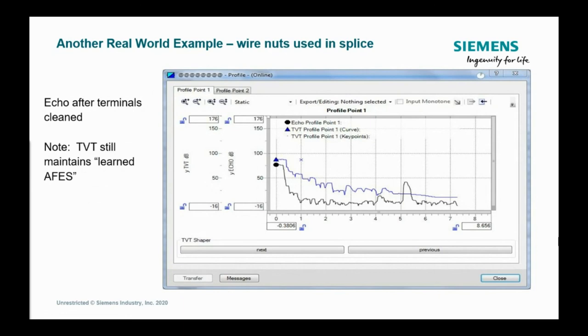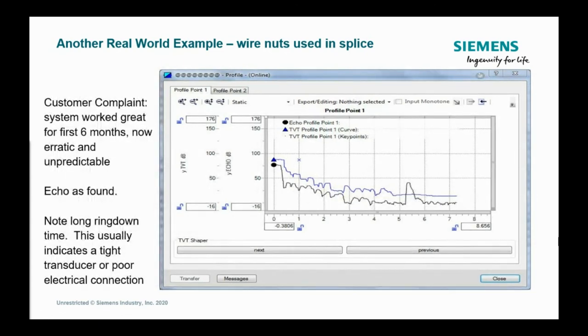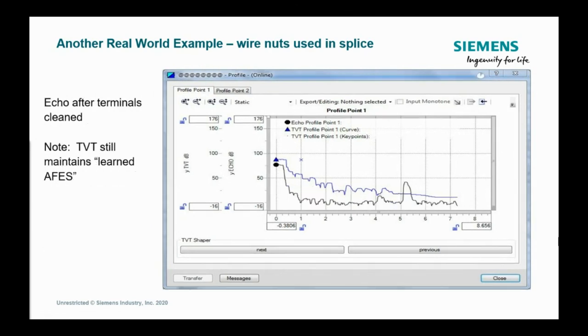What effectively is happening is wire nuts are really a bad splice for the transducer cable. Because especially in wastewater, you have a little bit of H2S gas. What does H2S do to electrical connections? It actually creates a little bit of resistance. Resistance equals a voltage drop. A little bit of voltage drop is going to take the transducer, take the instrument, a long time to figure out, because it's trying to figure out what's happening with this voltage drop for the signal coming back.